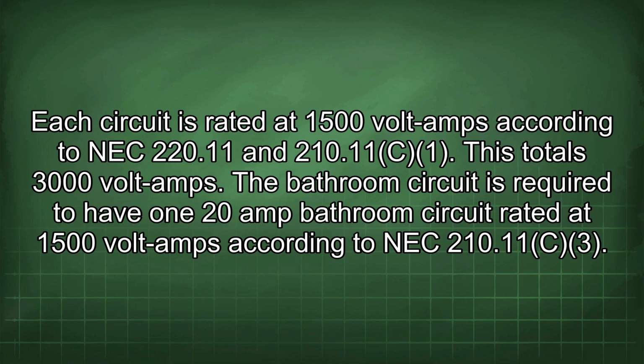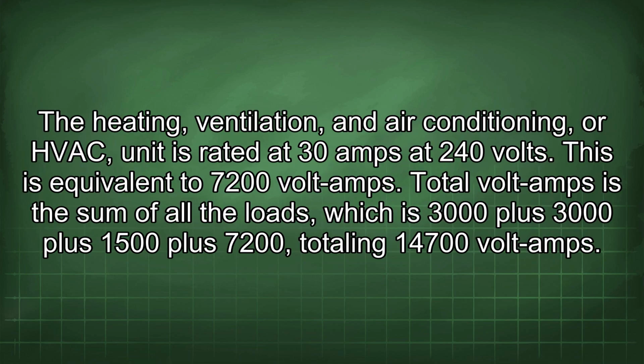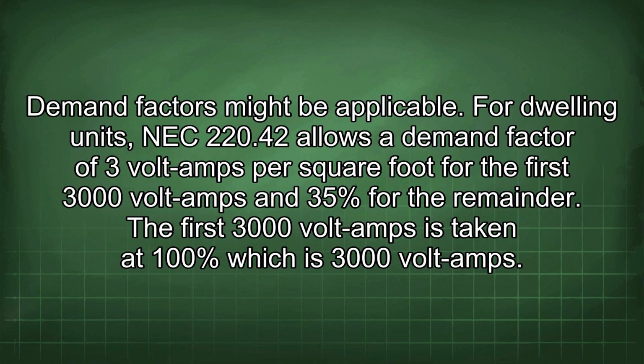The bathroom circuit is required to be a 20 amp, 120 volt bathroom circuit rated at 1500 volt-amps according to NEC 210.11(C)(3). The heating, ventilation, and air conditioning, or HVAC, unit is rated at 30 amps at 240 volts. This is equivalent to 7200 volt-amps. Total volt-amps is the sum of all the loads, which is 3000 plus 3000 plus 1500 plus 7200, totaling 14,700 volt-amps.